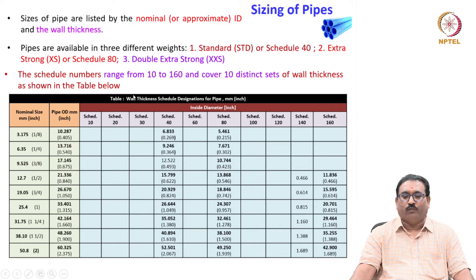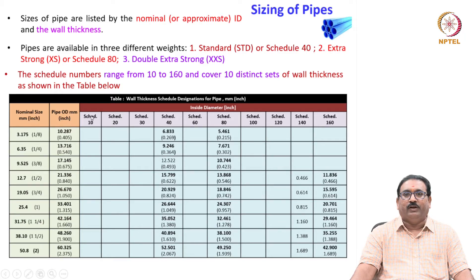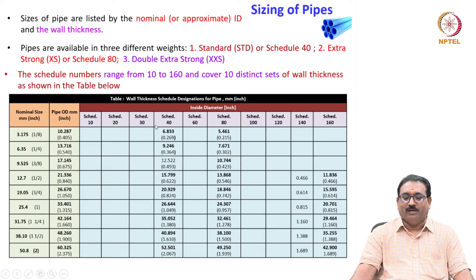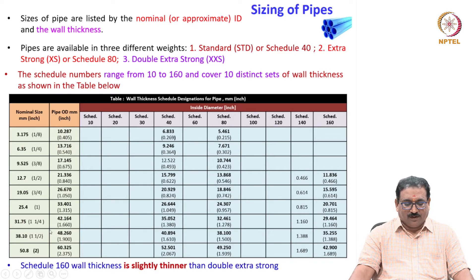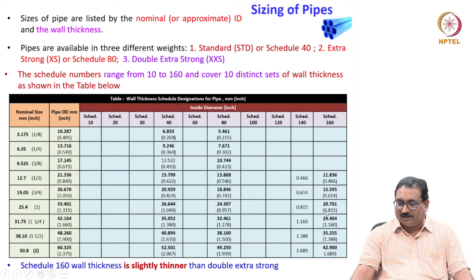This table shows the nominal diameter in millimeters and inches, the pipe OD, and schedule numbers 10, 20, 30, 40, 60, 80, 100, 120, 140, and 160 — these are the 10 distinct sets — along with the corresponding wall thicknesses in millimeters and inches. Note that the Schedule 160 wall thickness is slightly thinner than the double extra strong pipes.